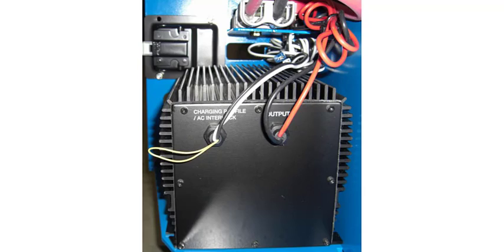This is a rear view of the Signet battery charger. Charger interlock wires are standard, but may not be installed on your machines. There is a female connector on one wire and a male connector on the other, that can be installed in line with the wire on terminal 1 of the DC motor controller. This interrupts machine operation while the charger is connected to a power source. This aids in eliminating the possibility of pulling the charger cord from the machine, while connected to an extension cord.